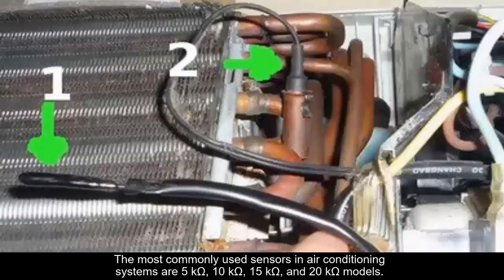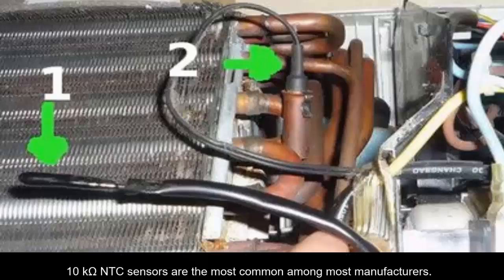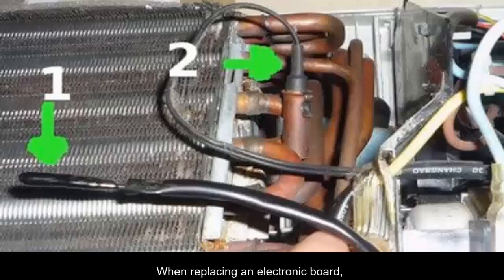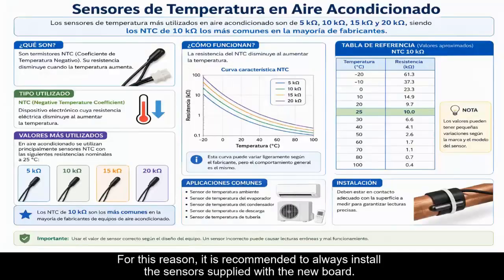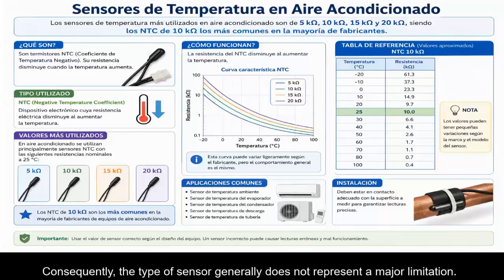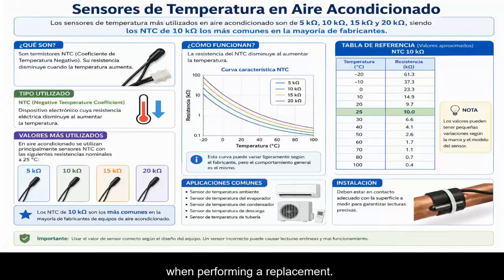The most commonly used sensors in air conditioning systems are 5 kiloohm, 10 kiloohm, 15 kiloohm, and 20 kiloohm models, with 10 kiloohm NTC sensors being the most common among most manufacturers. When replacing an electronic board, the new board normally includes its own temperature sensors. For this reason, it is recommended to always install the sensors supplied with the new board. Consequently, the type of sensor generally does not represent a major limitation when performing a replacement.